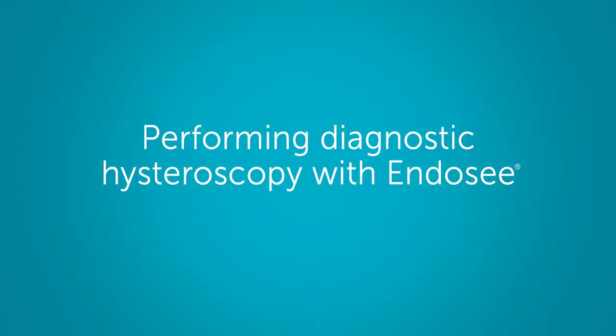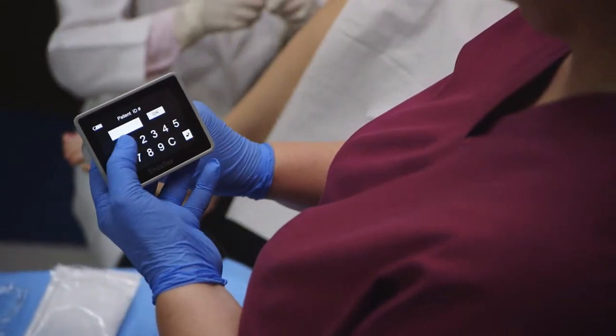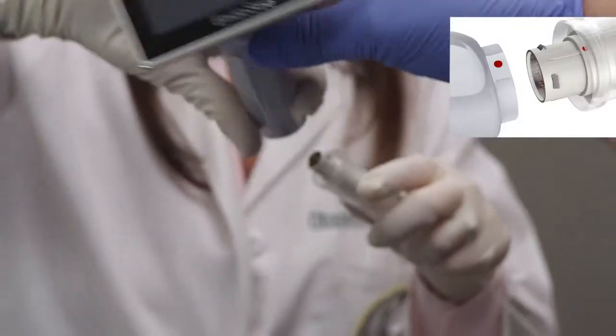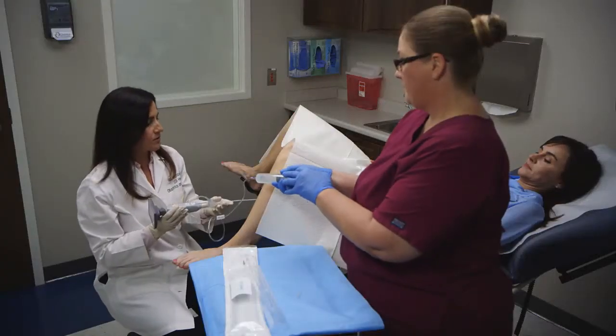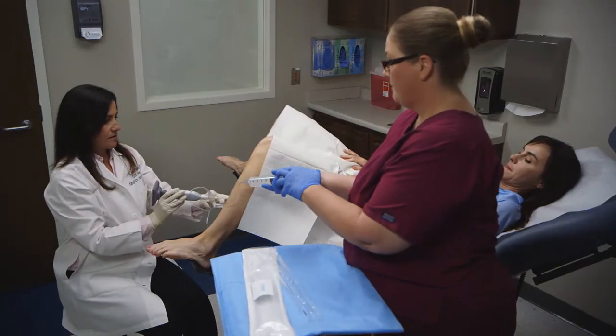You've seen how simple it is to set up for hysteroscopy with Endosee. Now take a look at performing hysteroscopy with this innovative device. To begin, turn on the Endosee handset and enter the patient ID number. Align the red dots to connect the handset to the cannula, then connect the tubing to infuse saline and purge the system of air. Endosee is now fully assembled and ready for use.